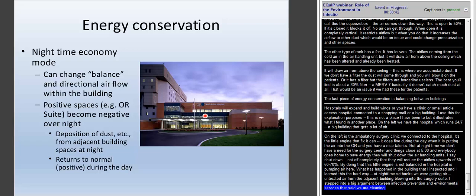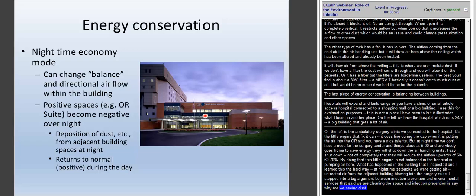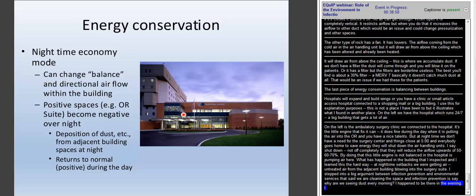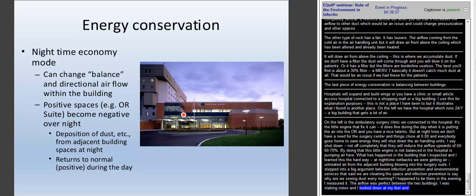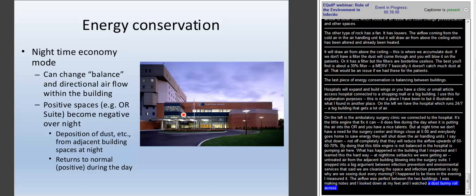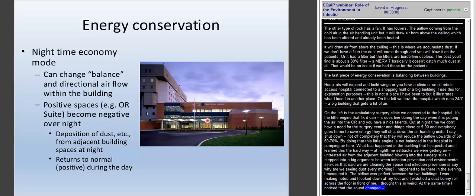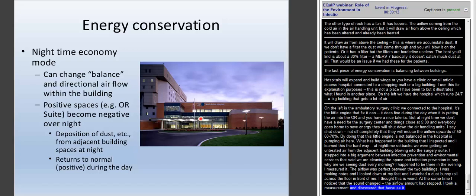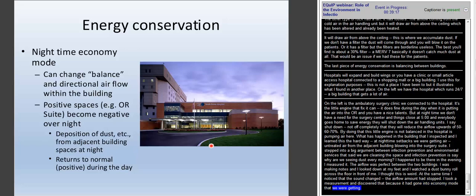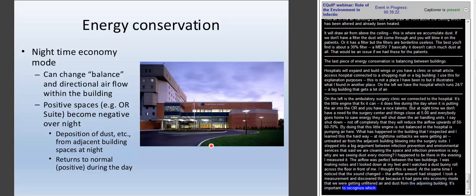So I happened to be there in the late evening, and I'm measuring it, and airflows were perfect between the two buildings, and I'm making some notes, and I look down at my feet, and I watch a dust bunny roll across the floor right in front of me, and I thought, well, that's weird. At the same time, I had noticed the sound changed, and the amount of airflow had stopped, so I went and corrected and took my measurements and discovered that because this had gone into economy mode, we were getting unfiltered air and dust from the adjoining buildings. So it's important to recognize that the systems are working and they're properly balanced for both night and daytime.